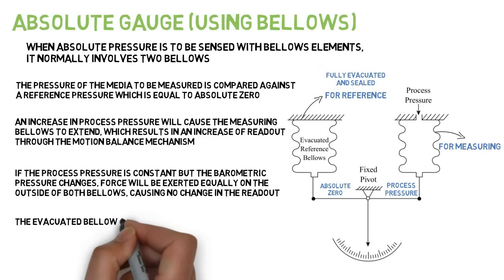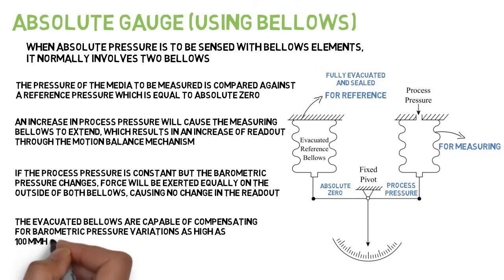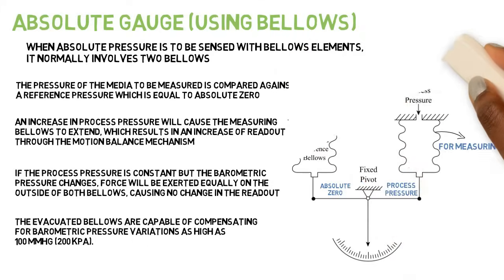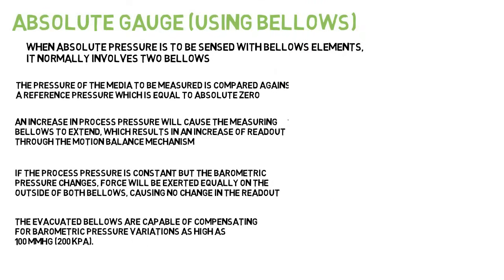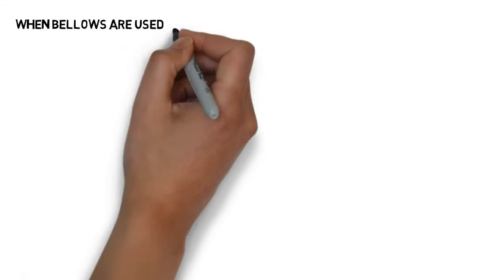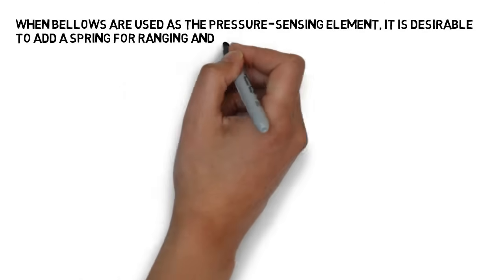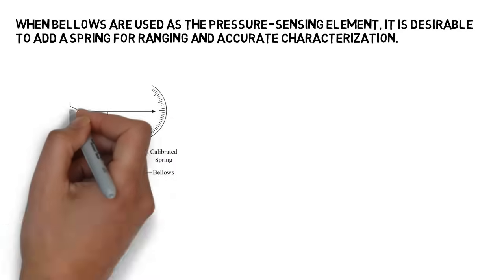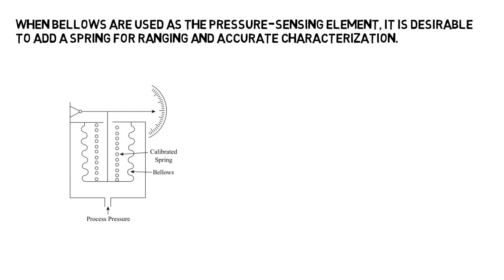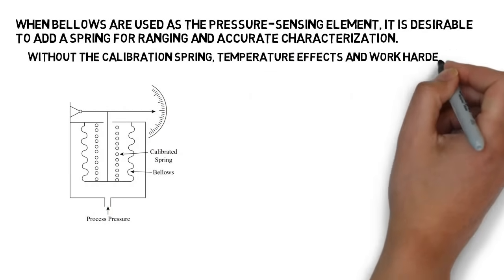The evacuated bellows are capable of compensating for barometric pressure variations as high as 100 millimetres of mercury. When bellows are used as the pressure sensing element, it is desirable to add a spring for ranging and accurate characterization. Without the calibration spring, temperature effects and work hardening of the bellows would cause a loss of accuracy.